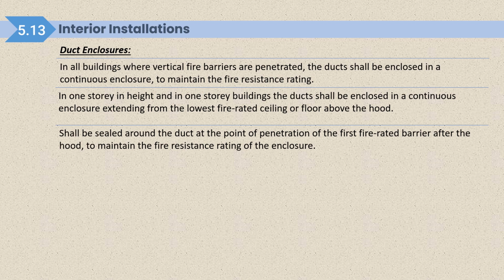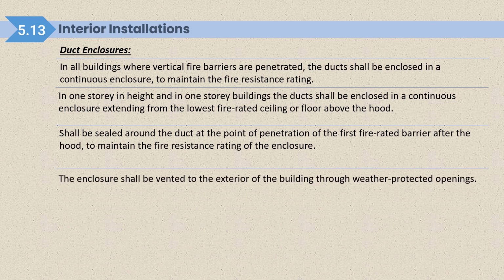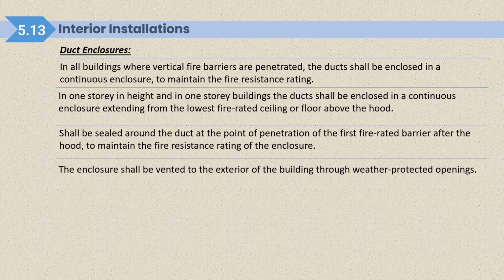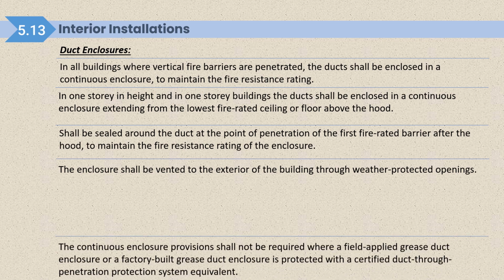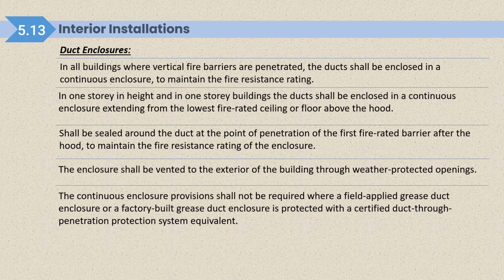It shall be sealed around the duct at the point of penetration of the first fire rated barrier after the hood to maintain the fire resistant rating of the enclosure. The enclosure shall be vented to the exterior of the building through a weather protected opening. The continuous enclosure provision shall not be required where a field applied grease duct enclosure or factory built grease duct enclosure is protected with a certified duct through penetration protection system equivalent.